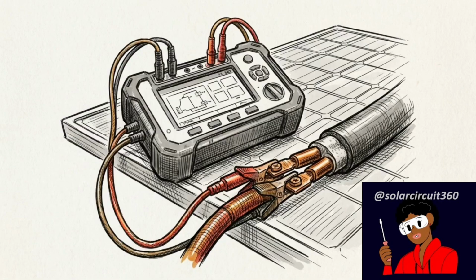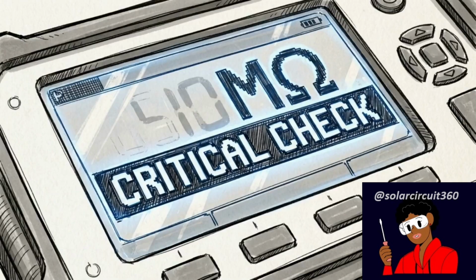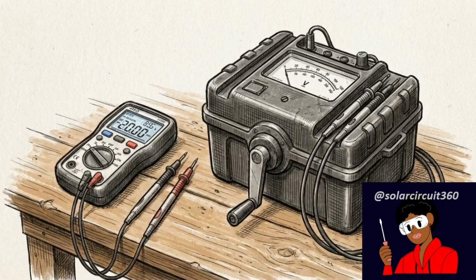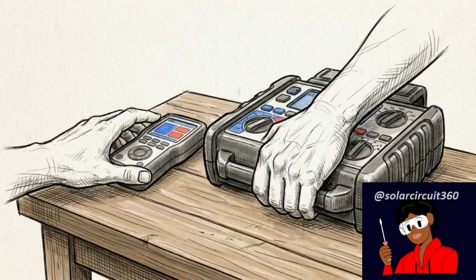To detect these hidden failure points, technicians must use a Megger tester to inject high-voltage DC into the cable. Interpreting this high-voltage response correctly provides a window into the health of the system's most vulnerable safety barrier. A frequent error in the field is treating an insulation resistance tester as a standard multimeter, essentially confusing a continuity check with a true insulation test.